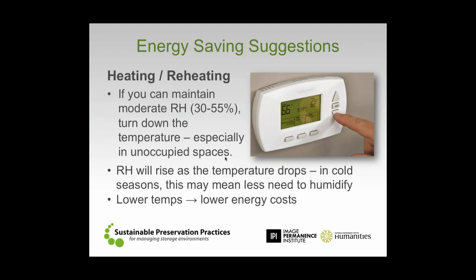Now, as we start to drop that temperature, the other thing that happens, especially in cold and dry climates, whether it's seasonal or all the time, is that as we drop the temperature, the relative humidity is going to start to go up. And if you're in a cold, dry environment, especially, looking at most of the entire northern United States in the wintertime and a large portion of Canada, parts of Europe, as we drop temperature, relative humidity is going to go up. And now all of a sudden we're also reducing the amount of humidification that we might have to do in a space. Or if we don't have any humidification, we're bringing the relative humidity up to a safer range. So that drop in temperature works in two ways: as an energy benefit, but also as a preservation benefit in terms of both relative humidity and slowing down the rate of chemical decay.